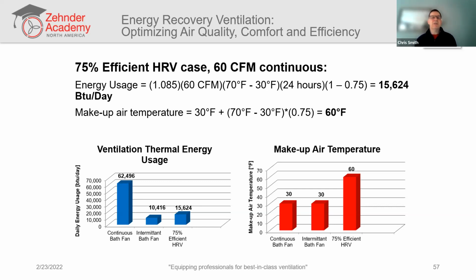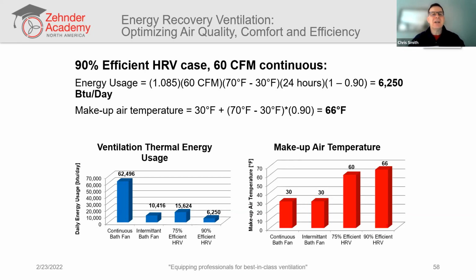So this 75% efficient HRV has dramatically improved our energy consumption and dramatically improved the comfort of our makeup air. What if we upped the ante and used a 90% efficient HRV? And these exist. Well, now we've reduced our heating load to even below what the intermittent 2-hour-a-day bath fan required, and we're improving our makeup air temperature even further. Now we're almost at room temperature. Our makeup air temperature is coming in at 66 degrees.